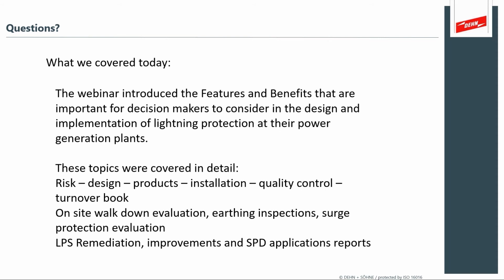Yes, I just want to mention, if we look at the general requirements of earth termination systems in the standard, remember that it mentions there that when we deal with lightning current, high frequency behavior, the shape and dimension of the earth termination system is the most important criteria. So in other words, they give us a 10 ohm recommendation, but from a viewpoint of lightning protection, we just need to make sure that we comply with a single integrated earth termination system that is the preference.